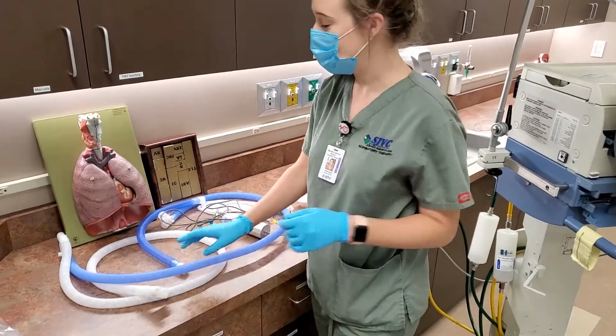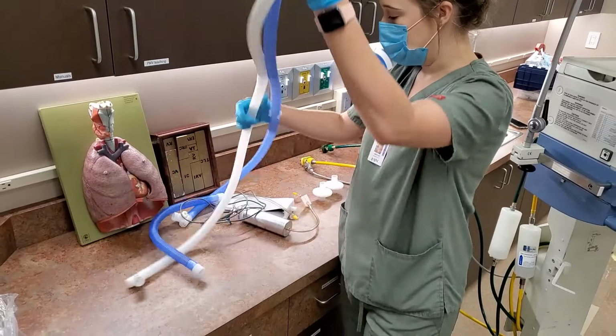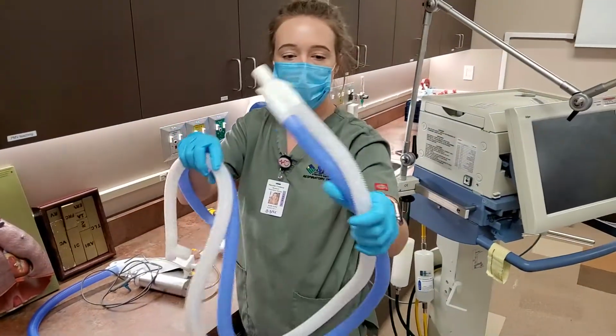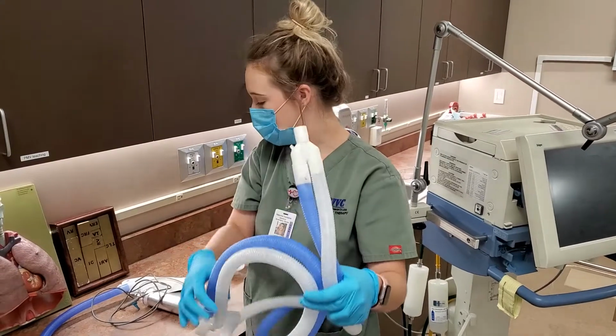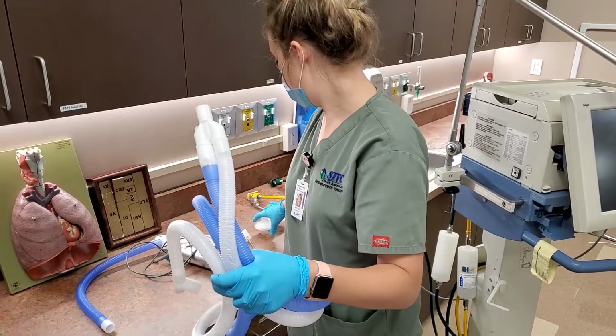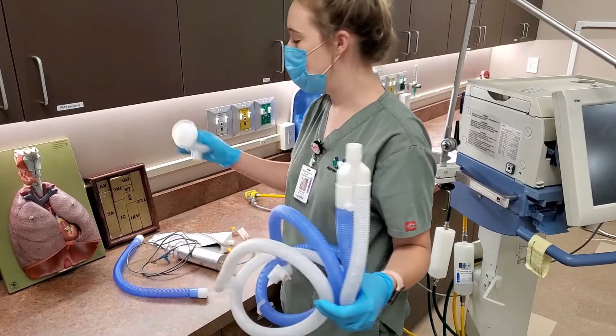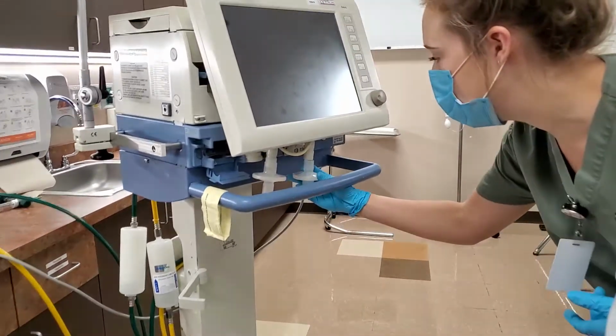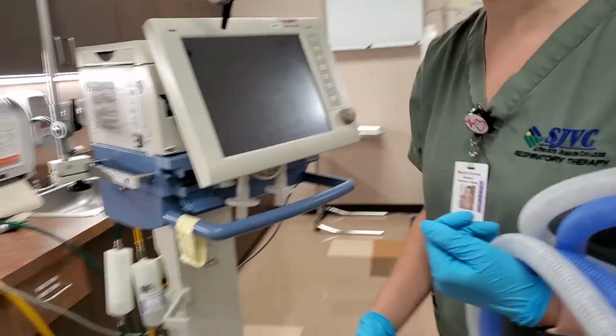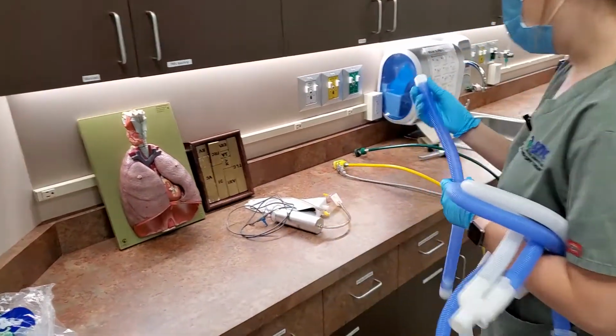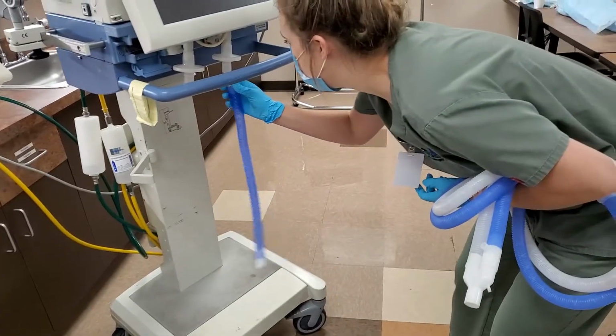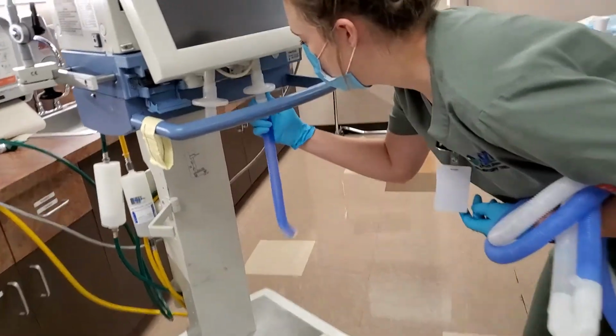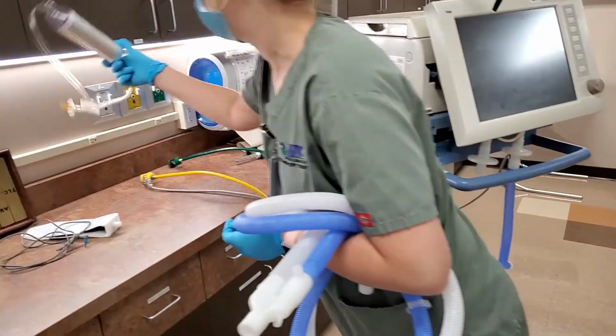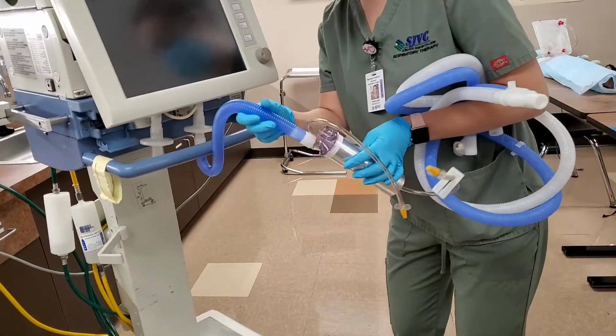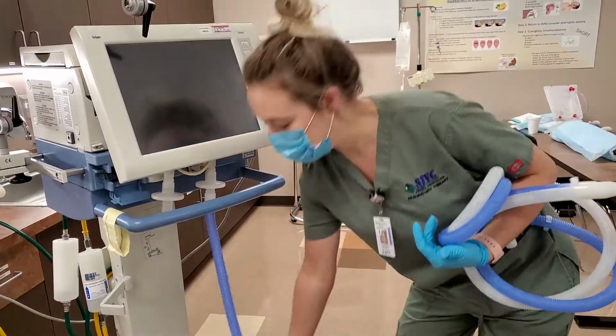So the first step to setting up the circuit, this is the circuit. This is what all the oxygen is going to go through. The first thing you do is get your HMEs, heat and moisture exchange, and plug them into the inspiratory and expiratory ports down here. And then you want to have your heater. You would connect this short corrugated tubing to one part of your heater. This is for the inspiratory side.